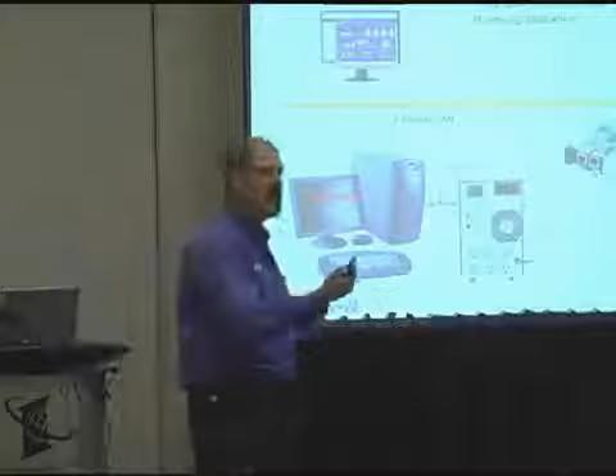Overload condition? Okay, let me turn off a couple of receptacles, do a little load shedding, and get this thing back up. Hey, my current draw on this plug went from 10 amps down to 0 amps. Why is that? Well, it's because my router locked up, the device isn't operating anymore. Okay, let me turn off that receptacle and turn it back on.